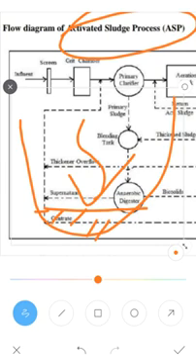BOD removal is evaluated based on the BOD of the aeration tank effluent and the BOD of the final effluent after sludge separation. In a properly operated activated sludge plant, the effluent will be very clear and sparkling, containing a very low amount of organic matter. This high quality effluent usually has a low BOD.